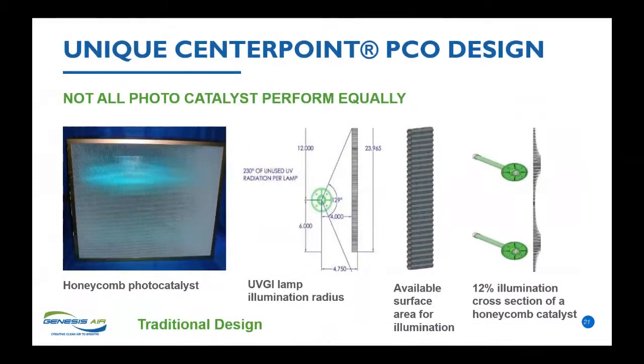Be aware there are other PCO products out there that do have good first pass effectiveness, only in the area where you see the light. So if you'll notice on the left, you can see the lights. I don't know if you remember in the other slide where it showed the CenterPoint PCO, the entire panel was illuminated, but you can see the illumination where the blue light shows through the honeycomb tunnels. You can also see the dark spots that are not being illuminated. So it affects first pass efficiency. Let's go to the next slide.